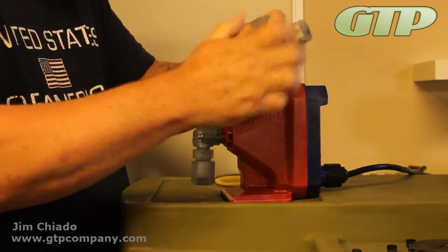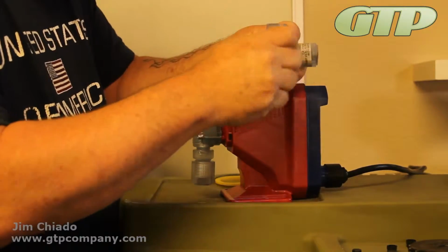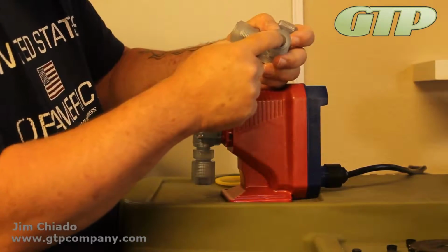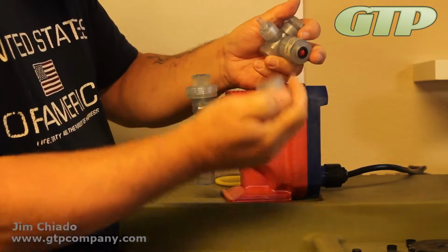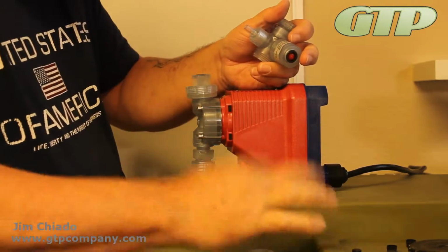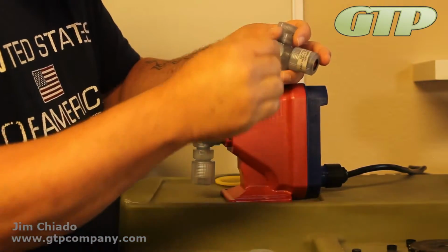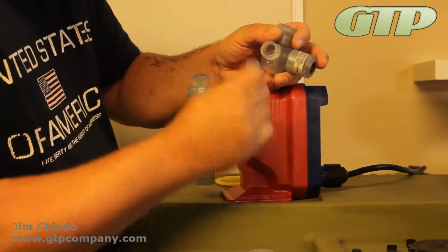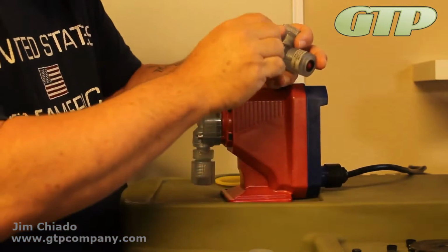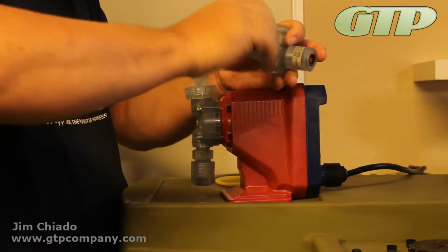Same thing on the air discharge side. Nothing different about it, but they just don't put this in. This holds in the liquid, there's no liquid coming off this side. You see there's a clamp ring, tubing clamp, nut, and the O-ring. Okay, put it back together.